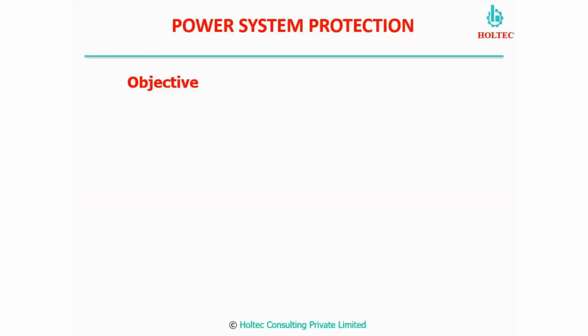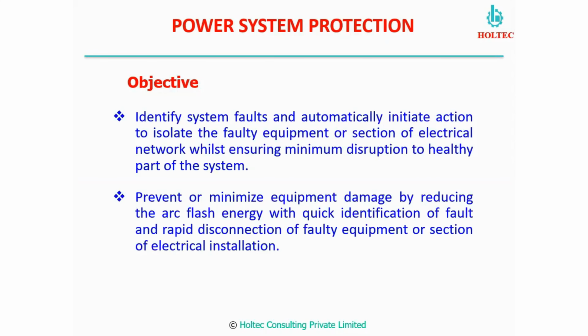Now coming to the protection, because we have covered short circuit, we have covered load flow. Now we can cover protections and relay coordination. So what is the objective of the protection? The objective is very clear. We have to identify the fault in the system. We have to automatically initiate the action to isolate the faulty equipment or the section. And the motive is that we have to ensure minimum disruption to the healthy part of the system. This is our main objective when we do the protection system design for a particular power distribution system.